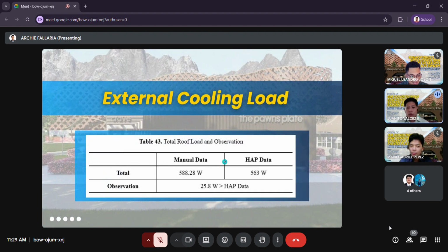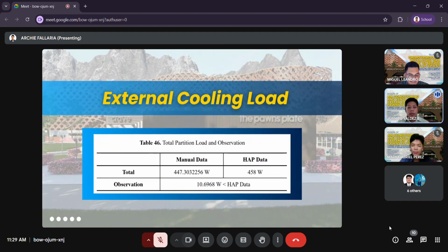Next, for our partition load, the table showing the total partition wall load illustrates the heat gain between conditioned and unconditioned interior spaces, such as the kitchen and storage area. Manual computation yielded a total of 447.30 watts based on the U values of interior partition walls and doors, along with the temperature difference between spaces. The HAP result is slightly higher at 458 watts, showing approximately 10.70 watt difference.